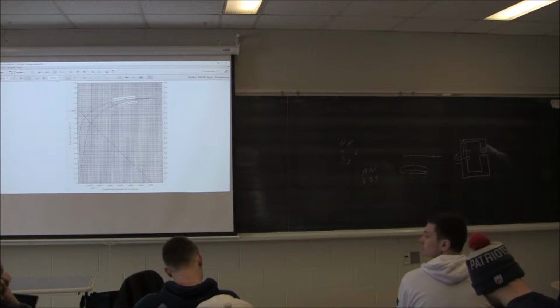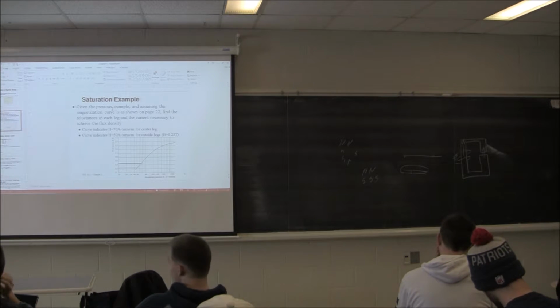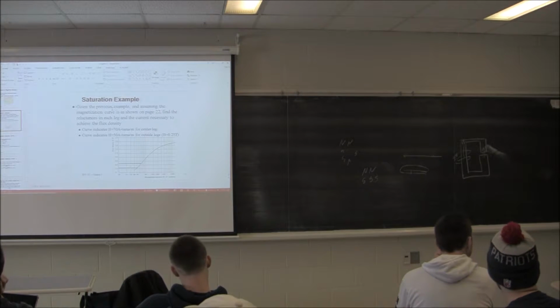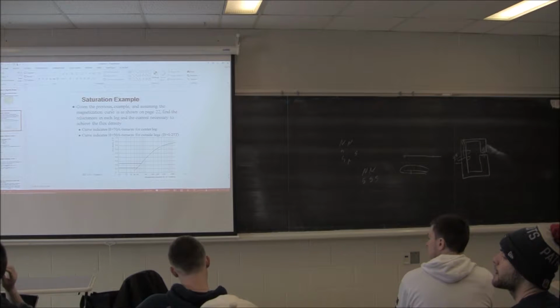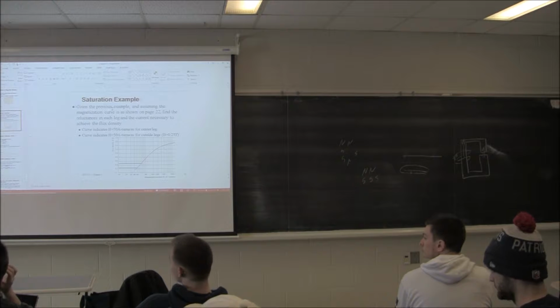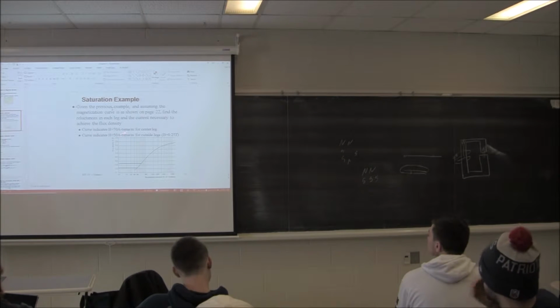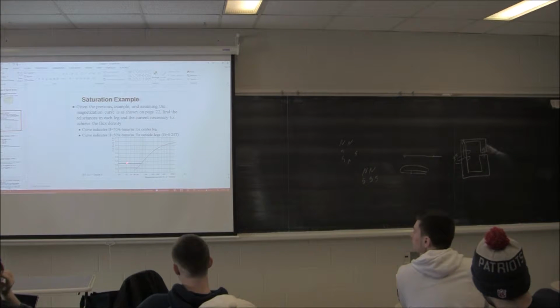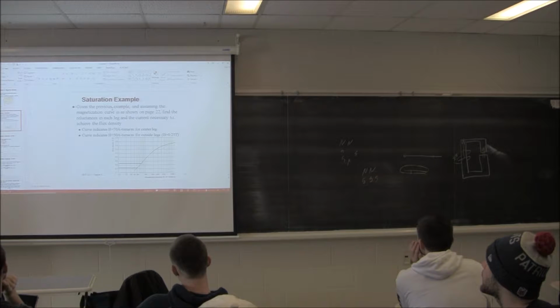It's specific on the steel. I know I may be asking a lot, but would you be able to describe how you go about doing that? Sure. Because how I got it was I went all the way to the top, assuming that it was 1.75 meters squared, and I ended up at 7,000, which was maxing it out. No, it's not that high. Okay. It's the same approach here, right? We figured out what the amp turns are going to be for a flux density. So once we have the flux density, we can pull off those values.